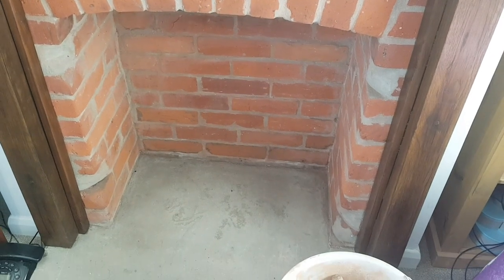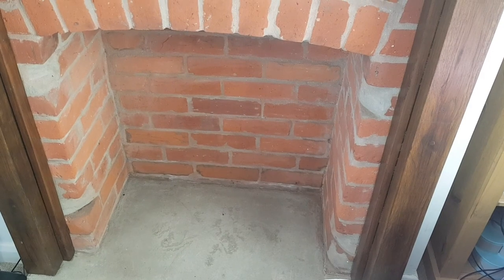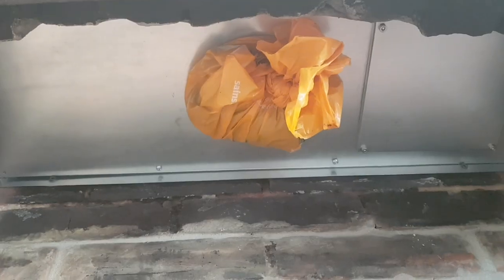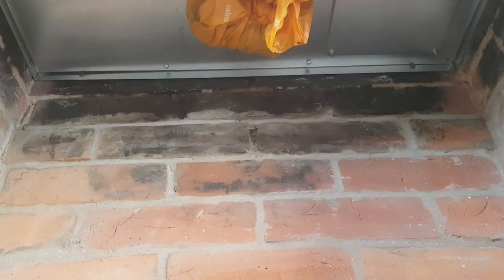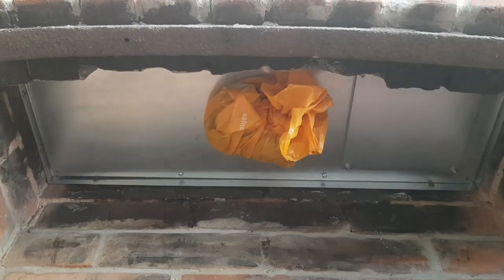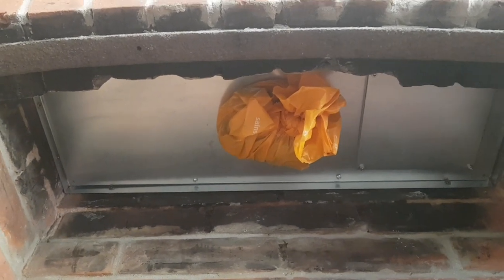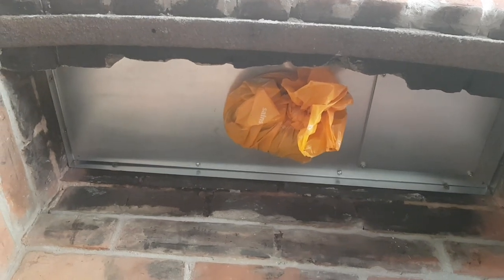This is the beginnings of my home install of a log burner and all of the flue. You can see I've put the register plate in — I want that just to stop stuff dropping down — because I'm putting in a full 904 flue, which is the harder stainless steel version, so you can burn pretty much most things and it'll last a long time.